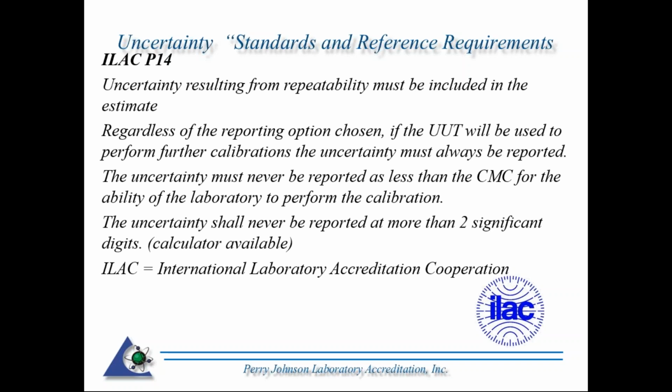Uncertainty resulting from repeatability must be included in the estimate, i.e., you have to include repeatability as a component to your uncertainty. Regardless of the reporting option chosen, if the unit under test will be used to perform further calibration, the uncertainty must always be reported. Hence, and this is something that needs to be determined during contract review, if your device is going to be used to calibrate other devices, then the uncertainty has to be reported. And if you recall the definition of traceability, that will need to be on those calibration reports.